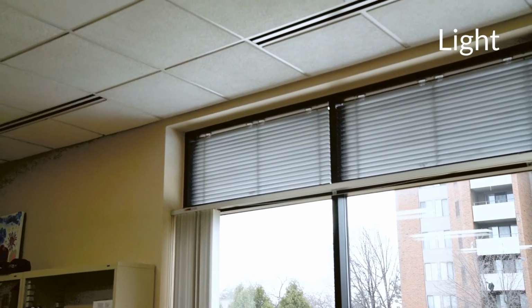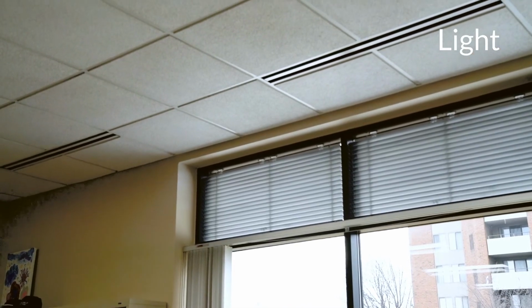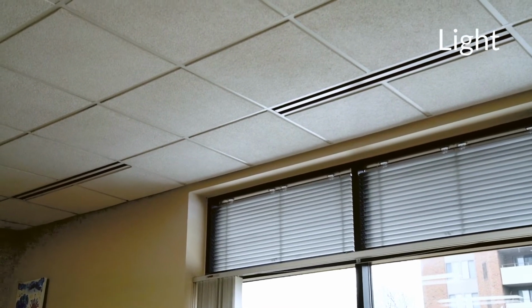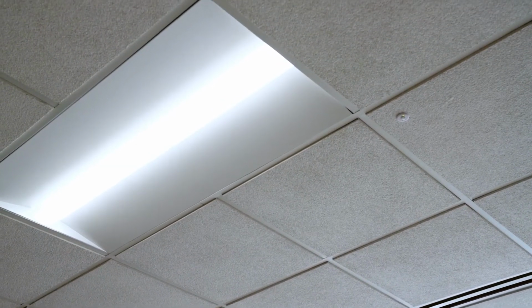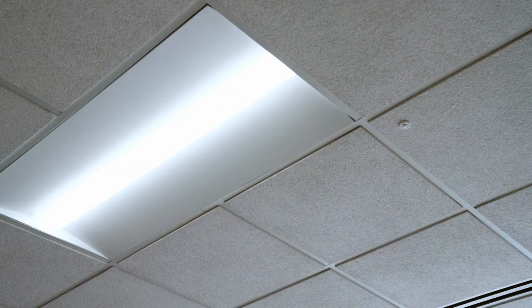The second sensing capability of our multi-sensor is ambient light. On the other side of the PIR sensor from the LED is a hole leading to the ambient light sensor. The ambient light sensor is to measure the light levels in the space below the sensor. This is useful near windows where sunlight coming in can help offset the need for light from your fixtures, saving you energy, allowing customers to operate in a more optimized, comfortable space. This energy saving strategy is known as daylight harvesting.